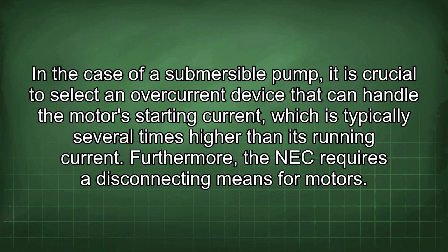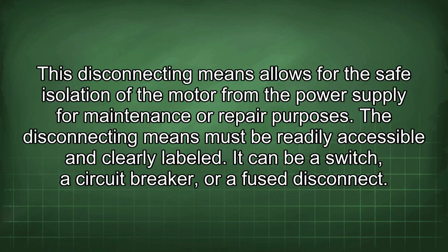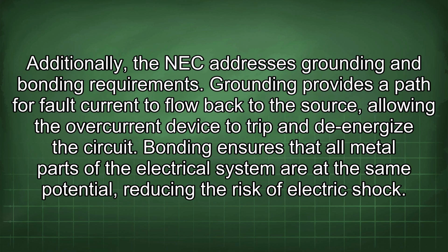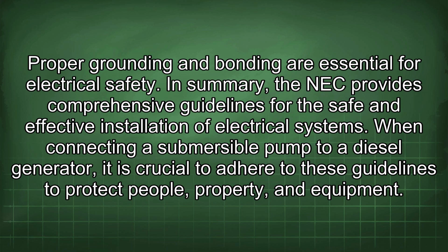Furthermore, the NEC requires a disconnecting means for motors. This disconnecting means allows for the safe isolation of the motor from the power supply for maintenance or repair purposes. The disconnecting means must be readily accessible and clearly labeled. It can be a switch, a circuit breaker, or a fuse disconnect. Additionally, the NEC addresses grounding and bonding requirements. Grounding provides a path for fault current to flow back to the source, allowing the overcurrent device to trip and de-energize the circuit. Bonding ensures that all metal parts of the electrical system are of the same potential, reducing the risk of electric shock. Proper grounding and bonding are essential for electrical safety.